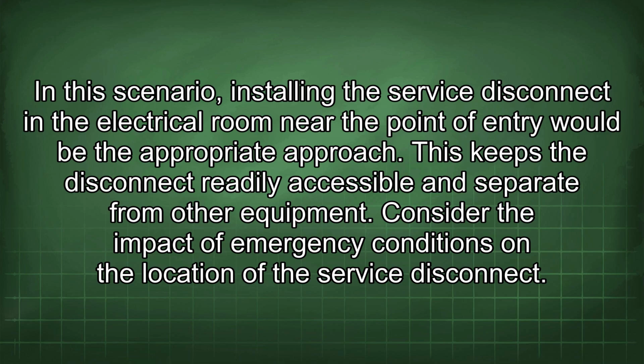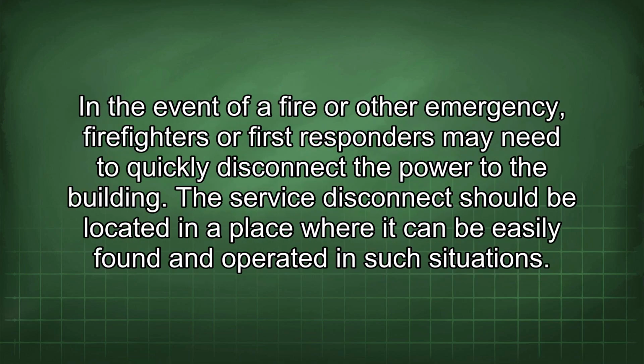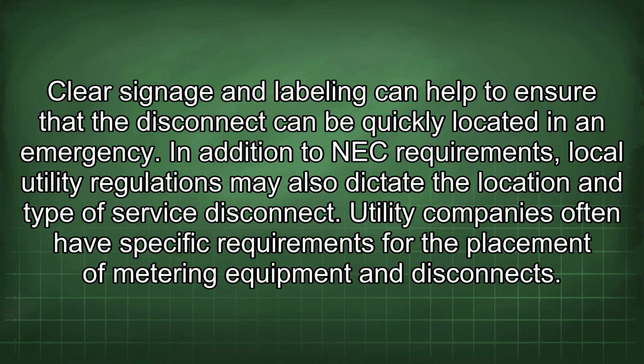Consider the impact of emergency conditions on the location of the service disconnect. In the event of a fire or other emergency, firefighters or first responders may need to quickly disconnect the power to the building. This service disconnect should be located in a place where it can be easily found and operated in such situations. Clear signage and labeling can help to ensure that the disconnect can be quickly located in an emergency.